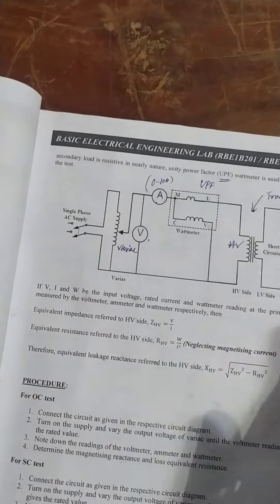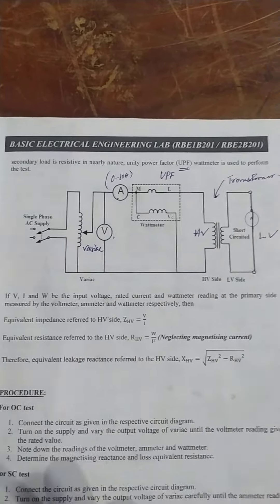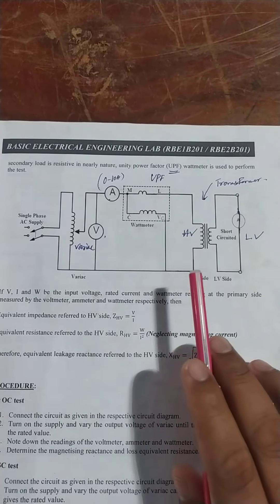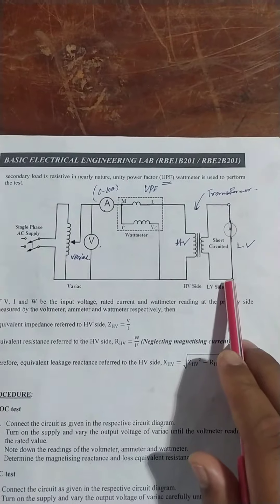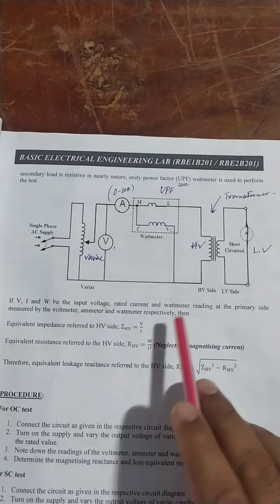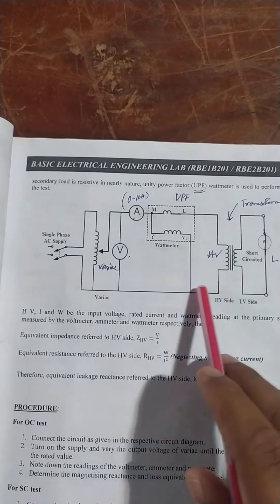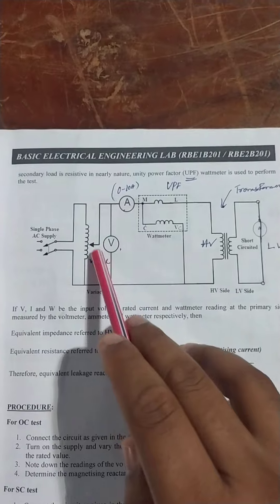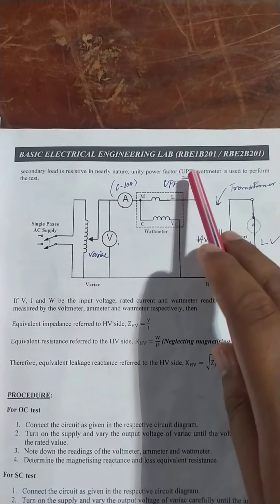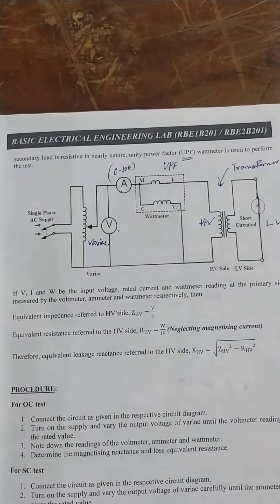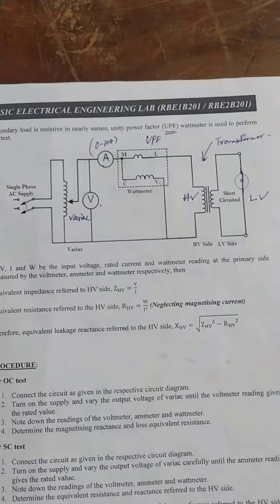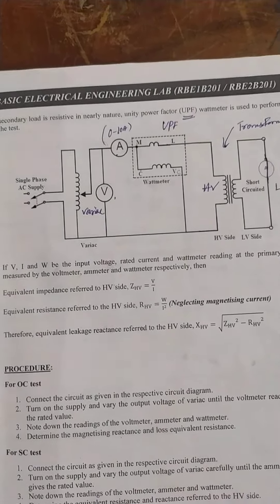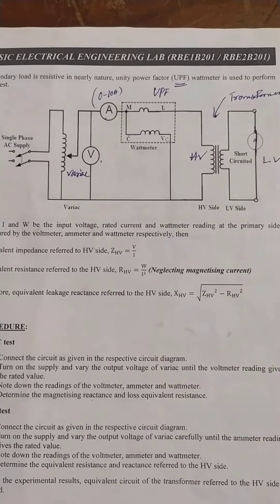Now moving to the short circuit test. The setup is similar, but here the LV side is short circuited — previously it was open circuited, now it is short circuited. On the HV side we connect the variac, voltmeter, ammeter, and wattmeter. In this case we use a UPF wattmeter because the power factor here is quite large compared to the previous test, where the power factor was about 0.2 to 0.3.